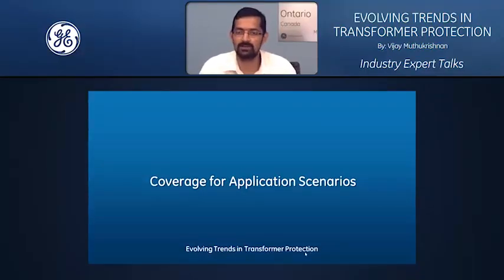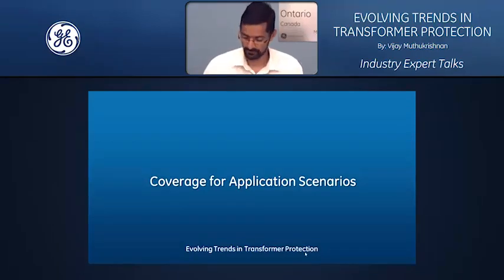Okay, having understood the core of the transformer differential functionalities, now let's move on to the coverage of applications. What I mean by coverage of applications is that the nature of a transformer and the way it fits into the context of your system has variability. You pick a particular application for your transformer protection based on the nature of your application. So I'm going to cover some typical scenarios that you come across and explain how varied it can be, and how a transformer protection relay should have the capability to fit all those types of applications so that the device you pick meets your requirements.